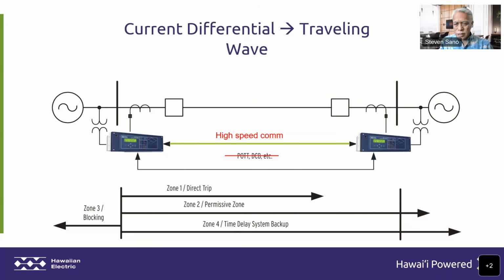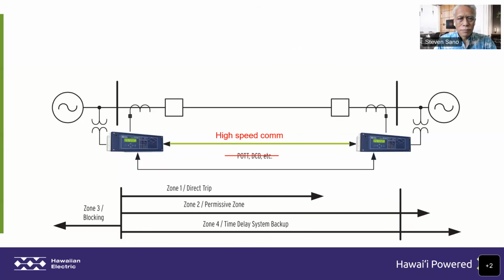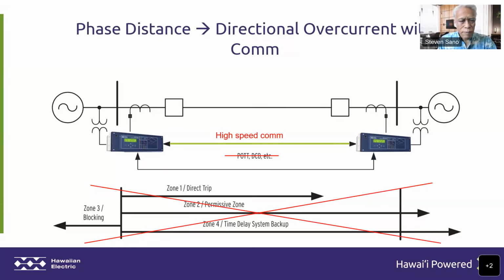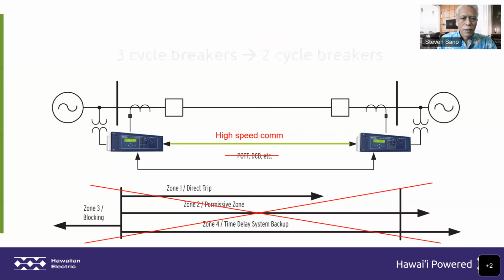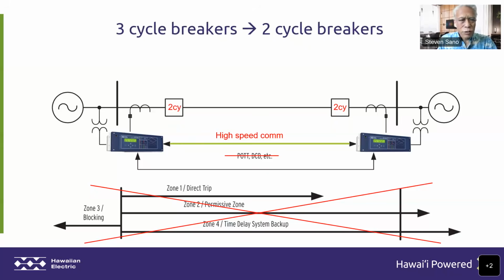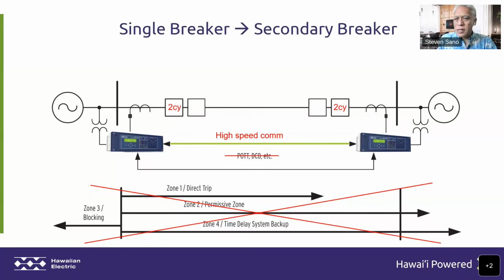If current differential is not sufficient, we'll have to go to traveling wave. Again, changing out the relays. Hopefully we changed out the COM adequately, and might have to change out the time source. Phase distance, that little diagram that you see at the bottom, showing our stepped zones there, might have to be replaced with things like directional overcurrent with communication, so supervised schemes requiring communication. Again, if things need to go faster, 3-cycle breakers get replaced with 2-cycle breakers. And if things have to go faster yet, we have to forego the breaker failure schemes and put in another breaker, which of course is always a challenge to do.